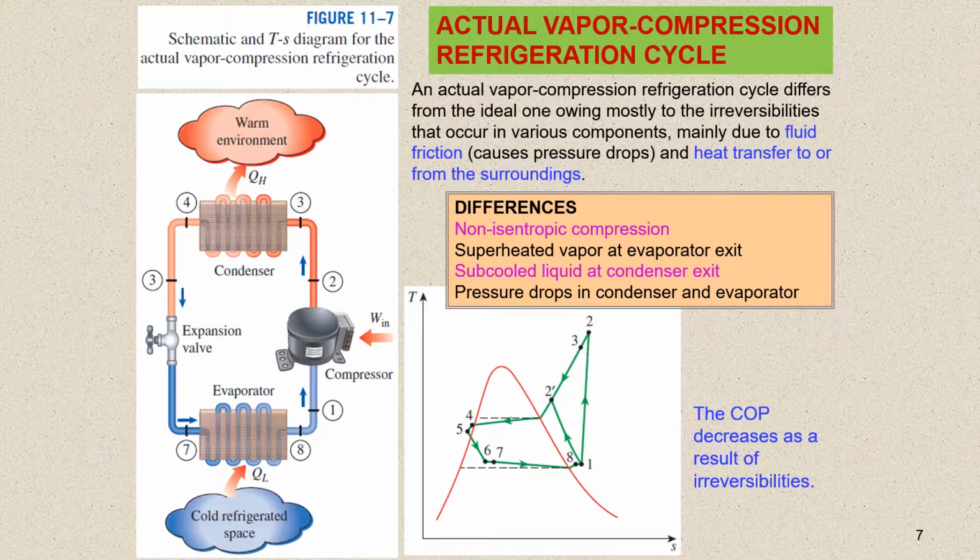We do not mind this at all, however, since the refrigerant in this case enters the evaporator with a lower enthalpy and thus can absorb more heat from the refrigerated space. The throttling valve and the evaporator are usually located very close to each other, so the pressure drop in the connecting line is small.